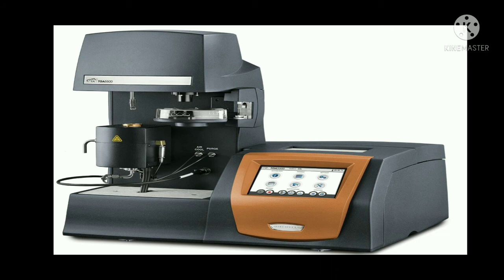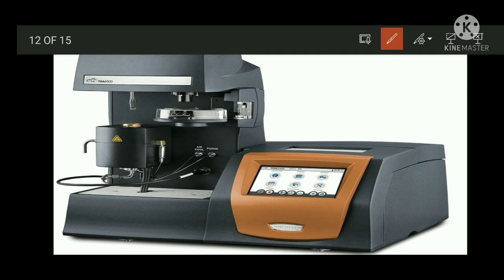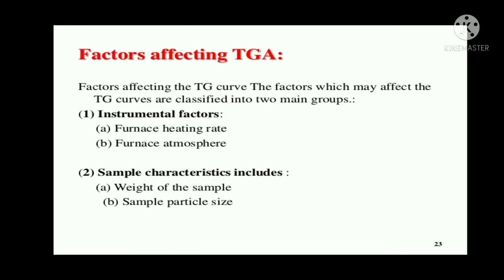This is a typical TGA instrumentation generally used in chemical industries for measuring the change in weight of the sample. Here is the pan over which the sample is placed, the thermocouple which controls the temperature, and the display over which we observe the change in sample properties. There are two kinds of factors which affect TGA: instrumental factors — which include furnace heating rate and atmosphere of the furnace — and sample characteristic factors — which include weight of the sample and sample particle size.